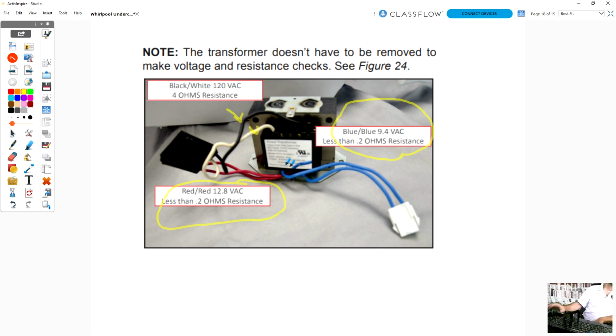How would you test it? Well, 120 in, and the two red wires would be 12.8 coming out, and the two blue wires are going to be 9.4 volts coming out. So that's going to serve power for our pumps, sensors, and everything else in the unit that does not run off of 120 volts.